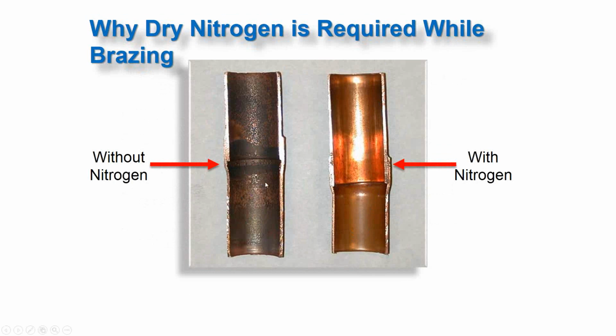If you do this and you do not purge with nitrogen, all of this black soot is going to get cleaned by the refrigerant. It's going to clean the inside of this pipe to look like that, and all this black soot is going to wind up back in the compressor. And if you get enough of it, it's going to turn to sludge, and it's going to lock up your compressor eventually, and you're going to need to replace your compressor, and that's going to be a nightmare. So always purge with nitrogen.